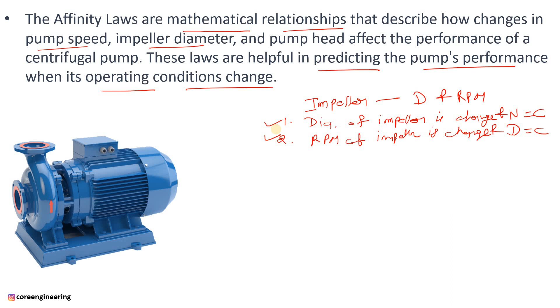So let's see the first formula, which talks about the flow rate. Q is directly proportional to N when the diameter of the impeller is constant. This means if you increase the RPM, your flow rate will increase. Let's see how with one example. Let's suppose Q1 is 10 cubic meter per hour, and N1 is your initial RPM, let's suppose 100 RPM. At N1 RPM, your flow rate is 10 cubic meter per hour. Then you change your RPM to 200. Now what will be the new flow rate?